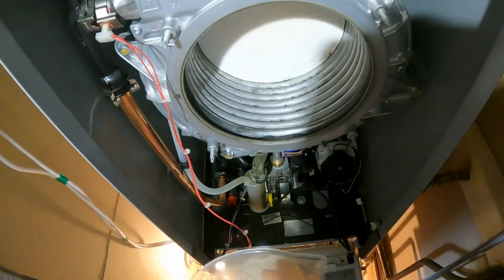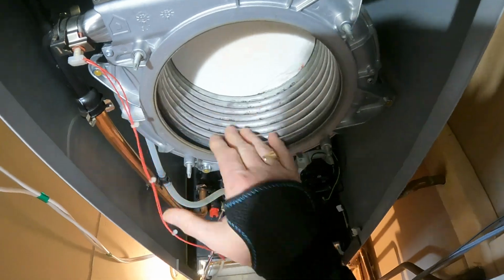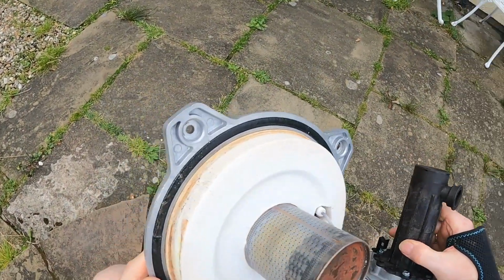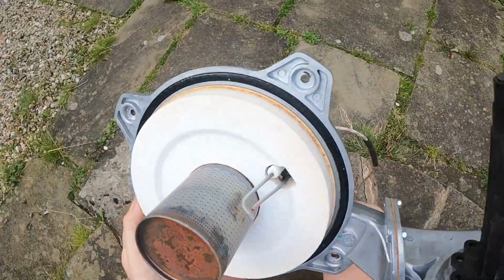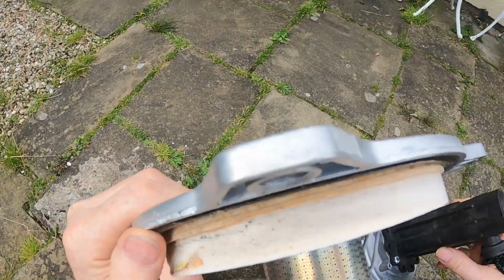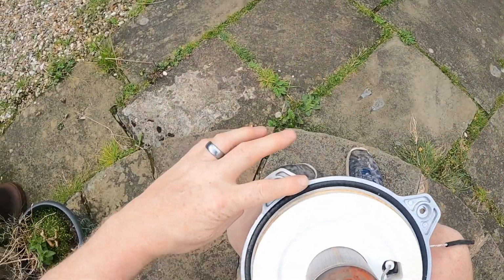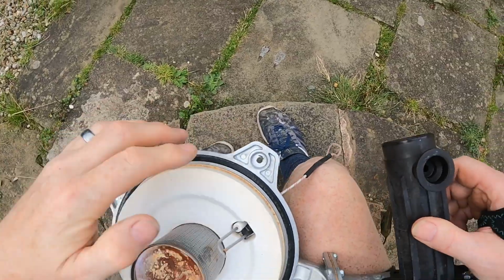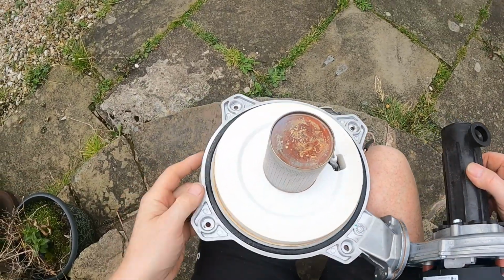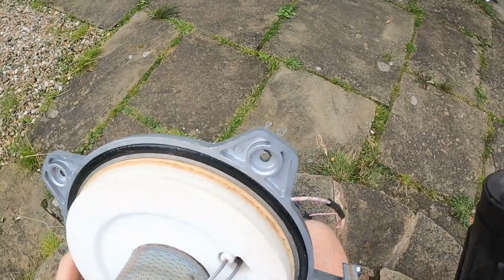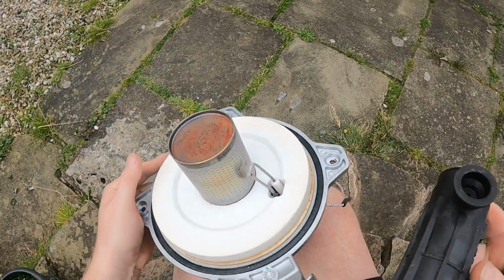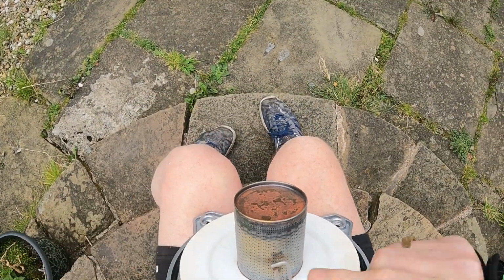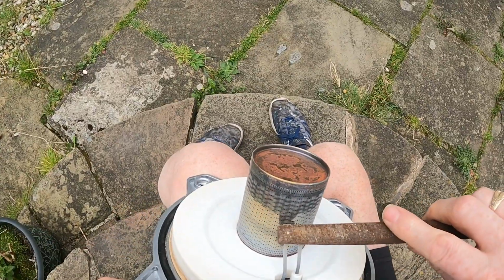So hopefully now that's a lot cleaner. Well, it looks a lot cleaner. So let's inspect the actual burner. So the burner looks in good nick. Seal is also good nick, still proud. And insulation looks good, but the electrode needs a little bit of attention.